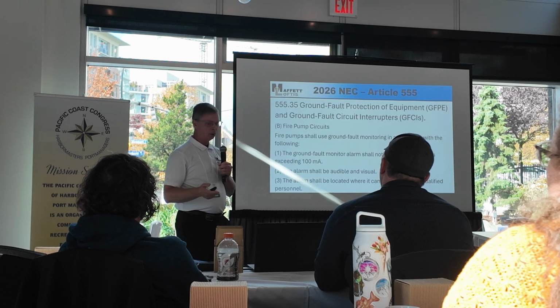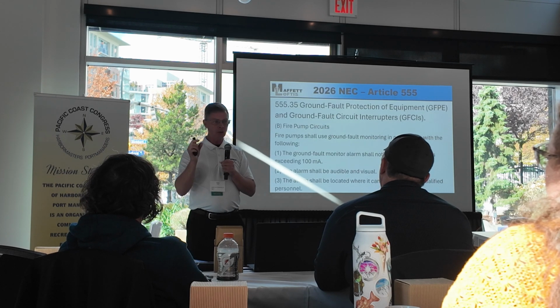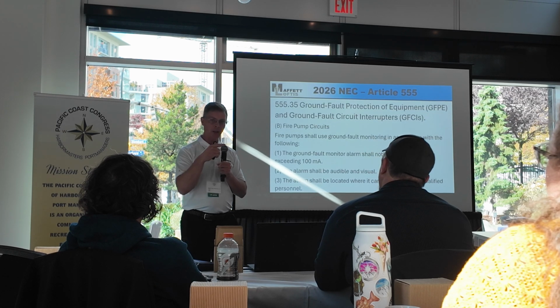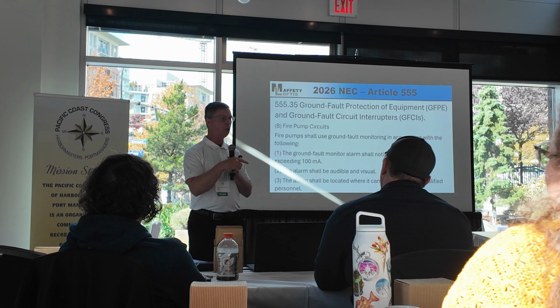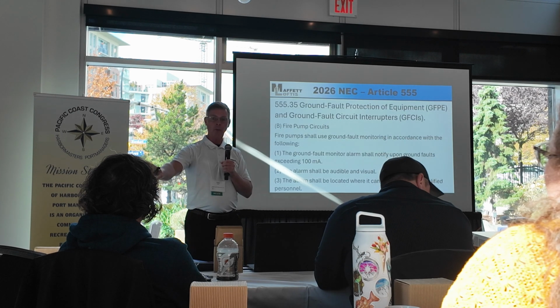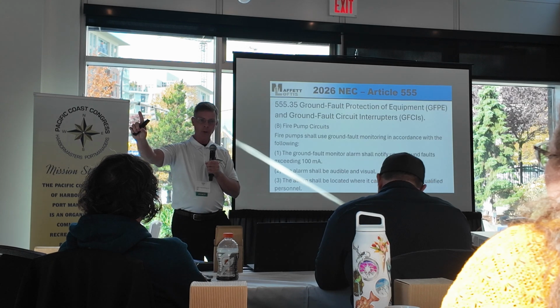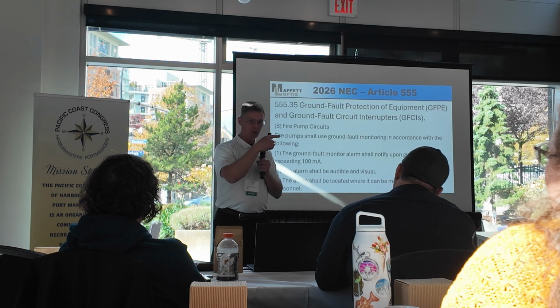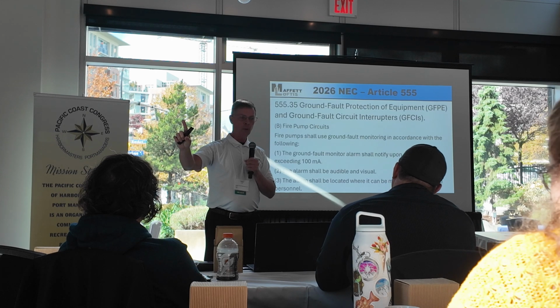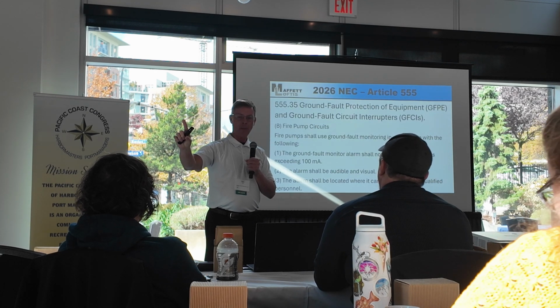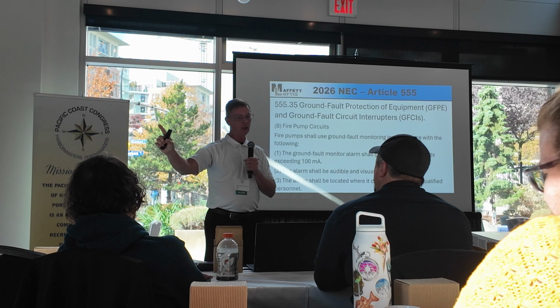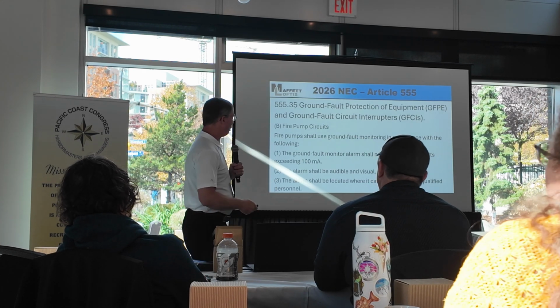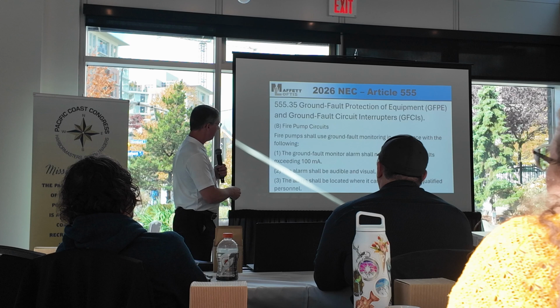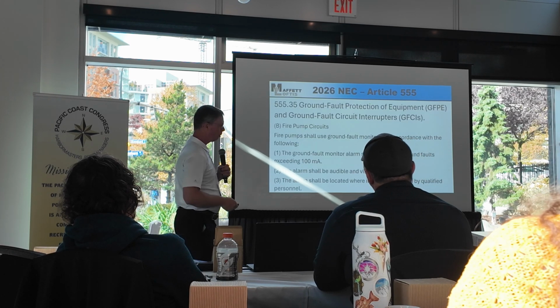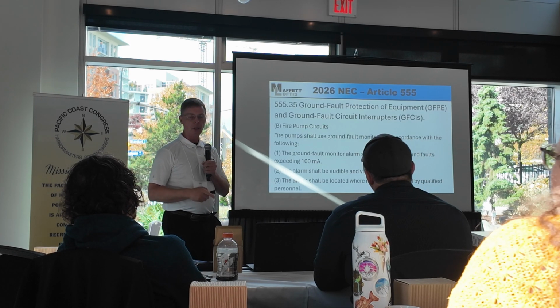Well, if you go down to the fire pump code 695, it says you cannot put GFPE in a fire pump because we don't want the fire pump to trip. But then we have electrical lines, actually unfused conductors, going from the service to the marina up to the fire pump by code. So I've got one code telling me I've got to do unfused conductors to a marina and put ground fault protection under Article 555, but another code says you can't put ground fault protection. So what we're saying here is that under Article 555, the fire pumps we want them to be ground fault monitored, but not ground fault protected.